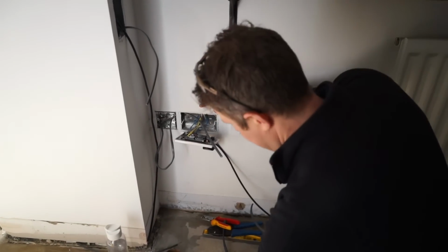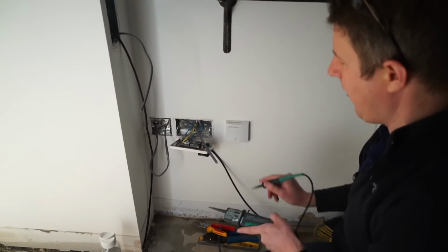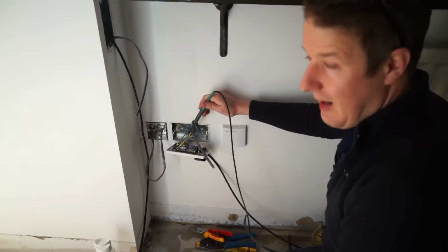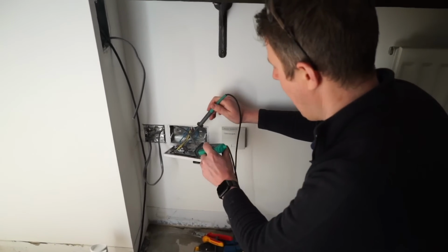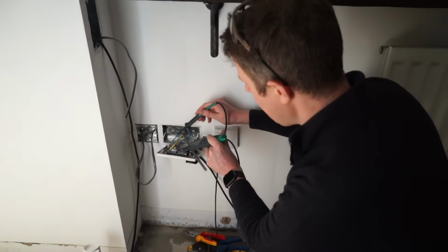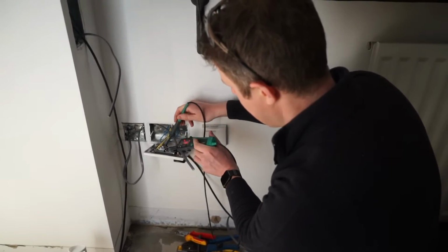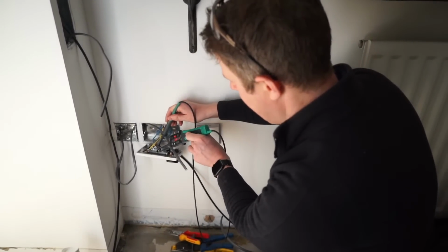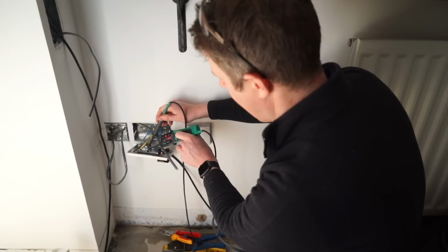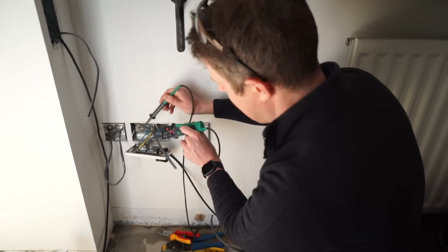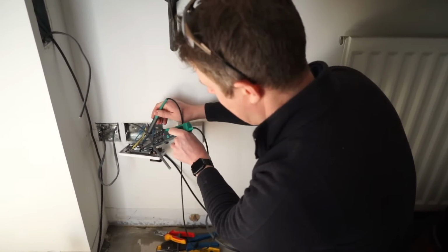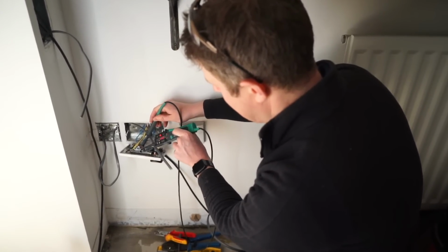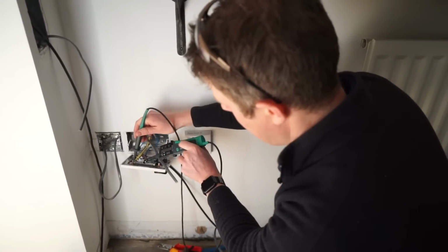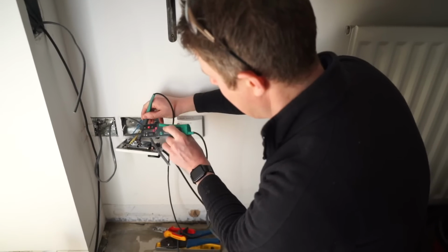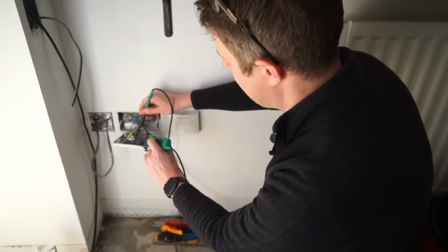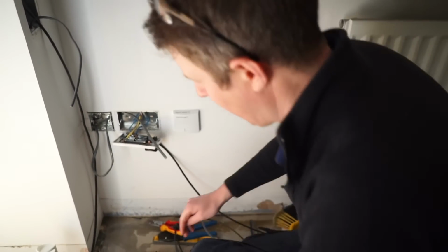Now this is live at the moment, and we obviously need to safely isolate it before we work on it. So I'm going to do a check to make sure my tester is working. You must always safely isolate a circuit when working on it. This is a GS38 voltage indicator, and we test line to neutral, line to CPC, neutral to CPC. So that is live. Now I'll turn the circuit breaker off.